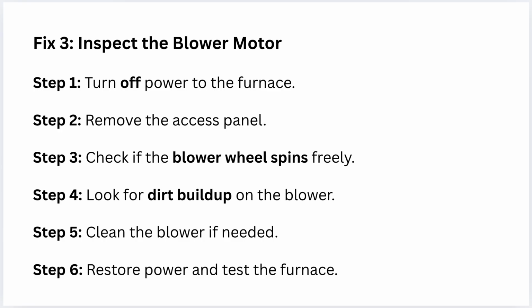Turn off power to the furnace, then remove the access panel. Check if the blower will spin freely. Look for dirt buildup on the blower. Then clean the blower if needed. Restore power and test the furnace.